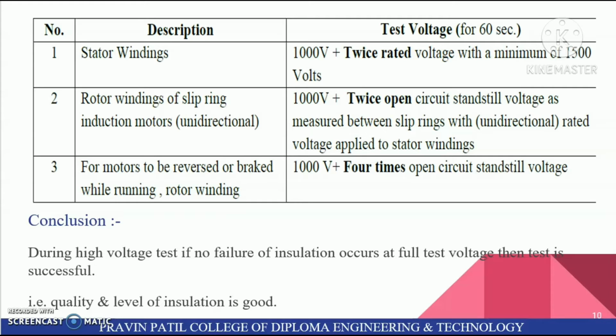open circuit standstill voltage. So the conclusion for this test is, during the high voltage test, if no failure of insulation occurs at full test voltage, then the test is successful, that is, the quality and level of insulation is good.